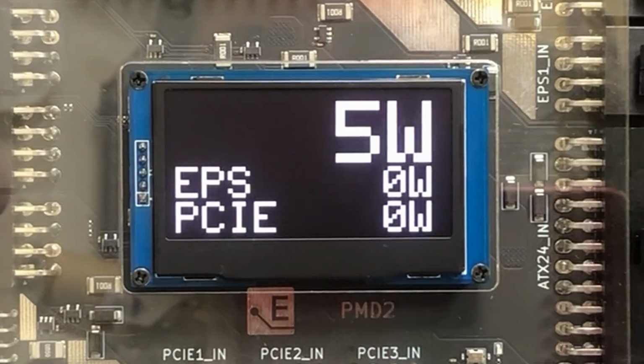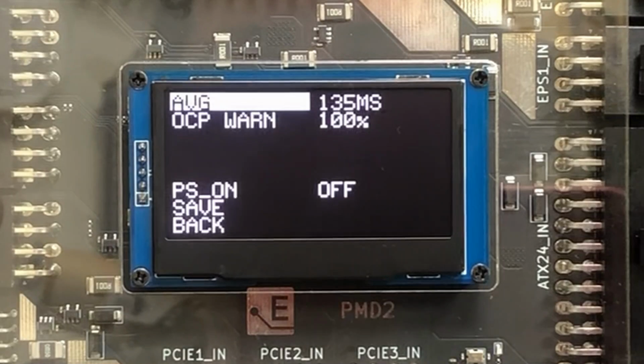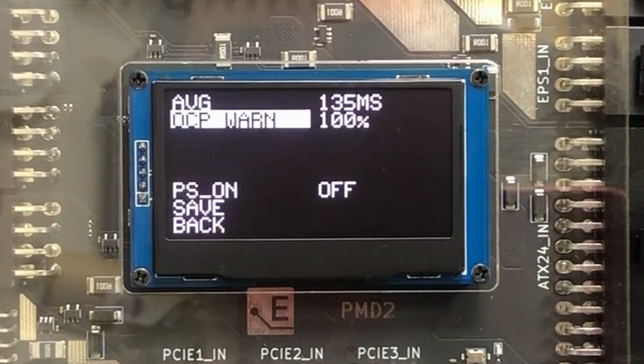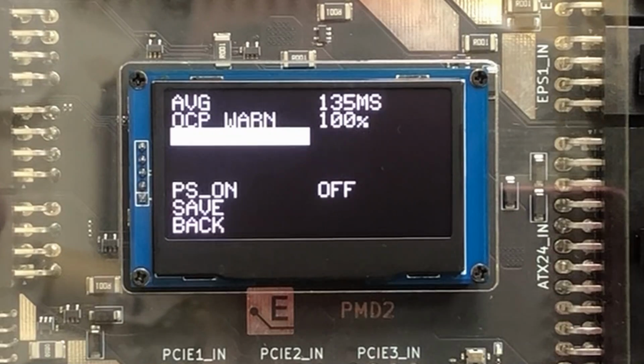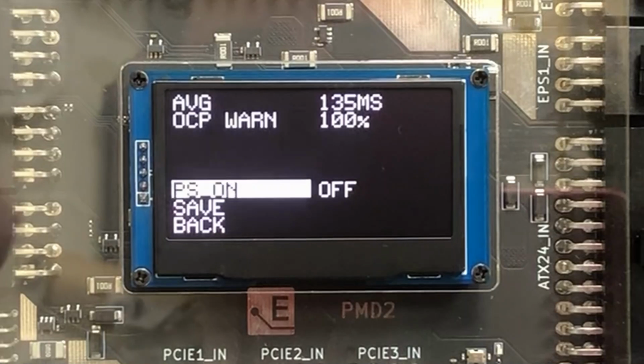There are 3 on-device configuration options. Average determines the measurement value update interval. The measurement value is the average of all values collected during the measurement interval. OCP warn sets the overcurrent threshold above which the OCP alarm will sound. PS on enables the PS on signal from the 24-pin ATX power supply cable, enabling the power supply.